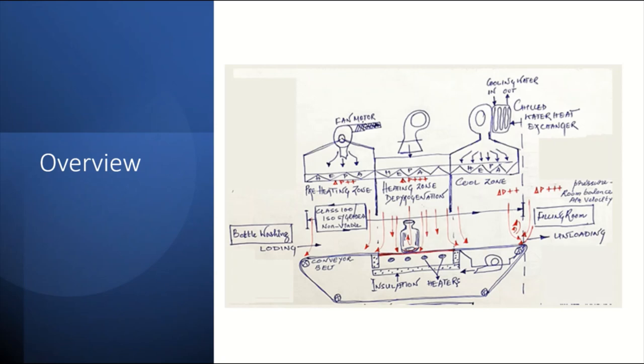This is a sketch, just a brief diagram showing the areas of the tunnel and how it is designed. We can see it has been installed in an area where this is your bottle washing machine, and this side is your filling room. This is a separate room with better control, and this is a moving dynamic conveyor which can deliver glass vials once they are getting depyrogenated.